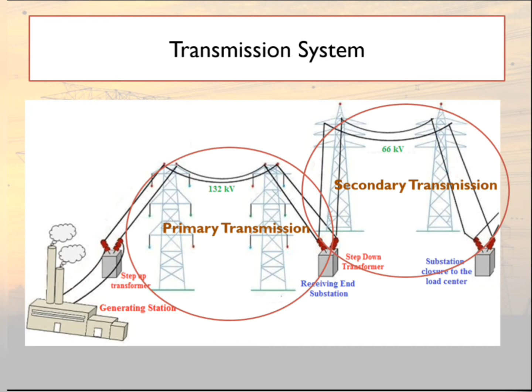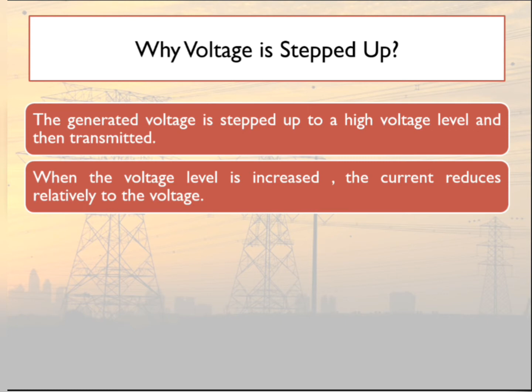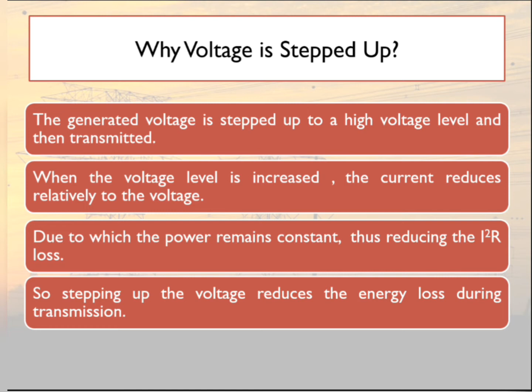Why do we need to step up the voltage in the generating station? The generated voltage is stepped up to a high voltage level and then transmitted. When the voltage level is increased, the current reduces relatively to the voltage, due to which the power remains constant, thus the I squared R loss is reduced. So stepping up the voltage reduces the energy loss during the transmission. So the voltage is stepped up in order to reduce the energy losses and also the voltage drop.